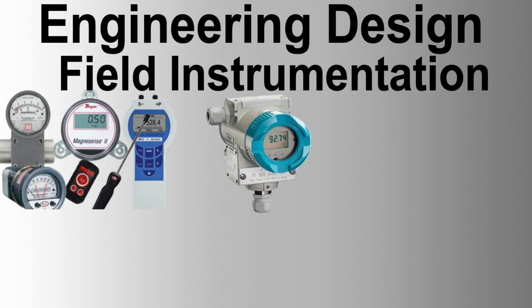Pressure and differential pressure instruments. Pressure and differential pressure, DP transmitters must be smart type with both analog and digital signal transmission using HART protocol, non-volatile memory, and self-diagnostic capability. The transmitter must be intrinsically safe, EXIA-IB certified, with a minimum ingress protection rating of IP65. The sensor must be diaphragm capacitance type with silicon oil fill fluid, and the body and wetted parts must be SS316 as a minimum, with Hastelloy C measuring element diaphragm. Process connections must be 1/2-inch NPT-F, and electrical cable entry must be ISO metric.